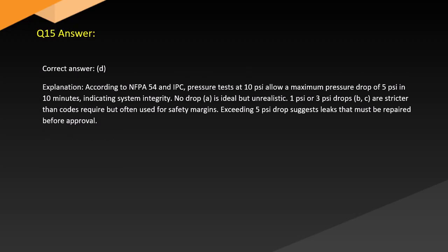Answer. Correct answer: D. Explanation: According to NFPA 54 and IFGC, pressure tests at 10 psi allow a maximum pressure drop of 5 psi in 10 minutes, indicating system integrity. No drop (A) is ideal but unrealistic. 1 psi or 3 psi drops (B, C) are stricter than codes require but often used for safety margins. Exceeding a 5 psi drop suggests leaks that must be repaired before approval.